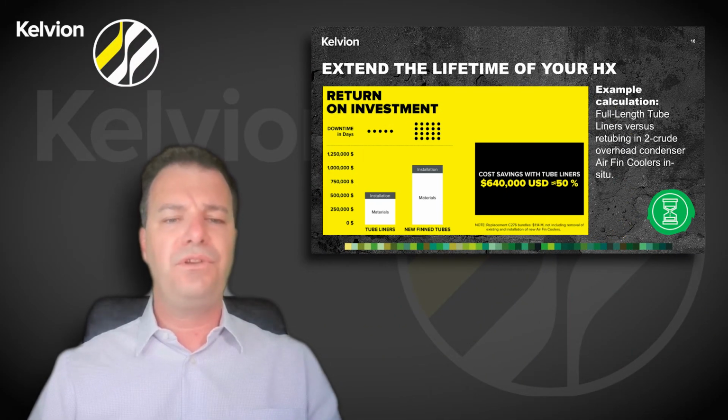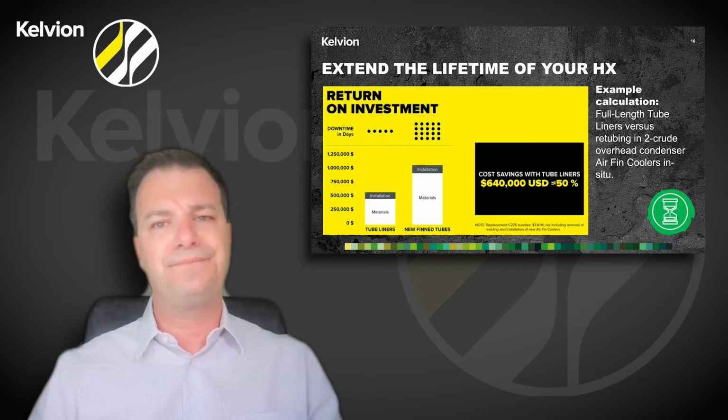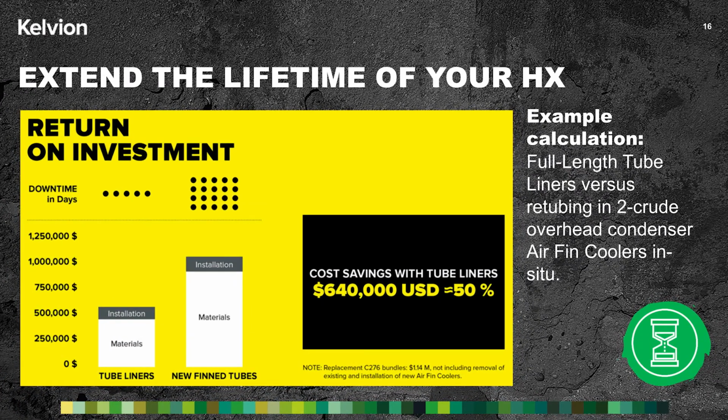Let me show you a good return on investment achieved when using CTI technology, just as an example. In detail, with regard to the main top column condenser that recovers heat from the top of the distillation column into crude oil feedstock, we evaluated the investment impact when comparing full-length tube liners with retubing.